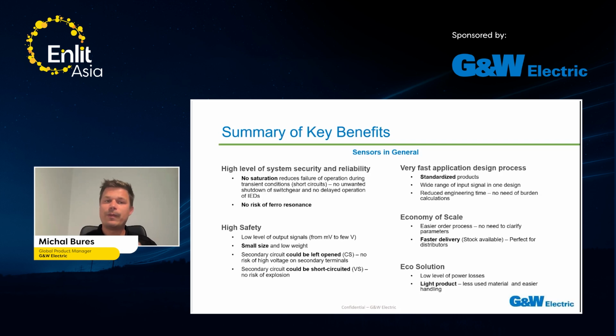So you have a high level of system security because there is no saturation and no risk of ferroresonance. The sensor is a very safe solution because the output signal is very low, so it's safe for the persons. It is small in size and low in weight, so you don't need to lift heavy weights. The secondary circuits for both current and voltage sensors can be left open or short circuited.